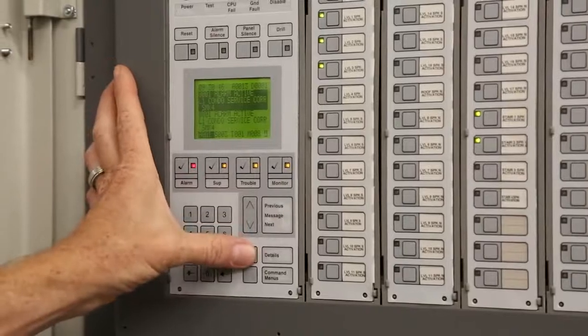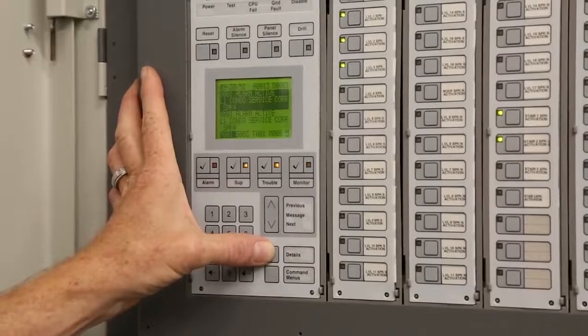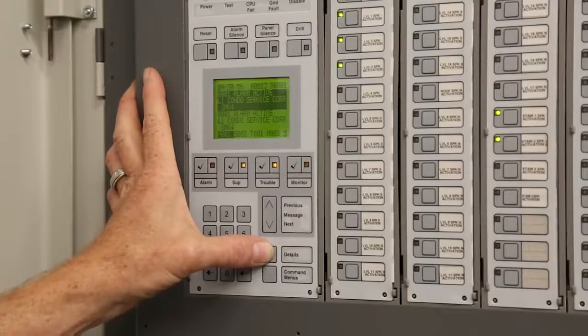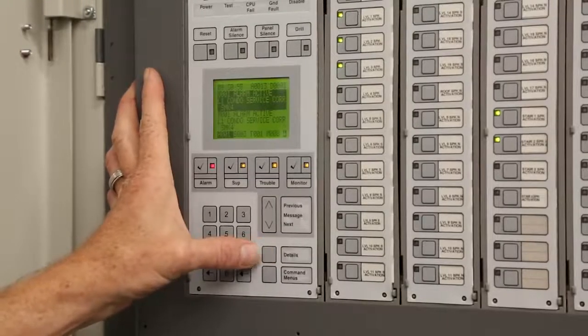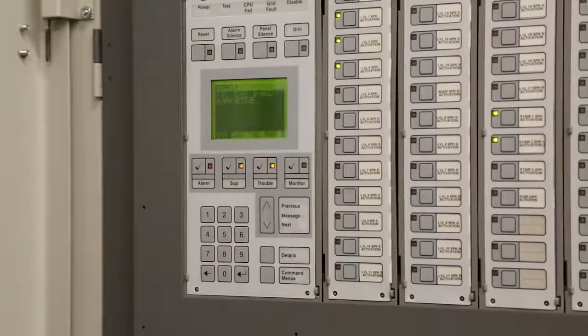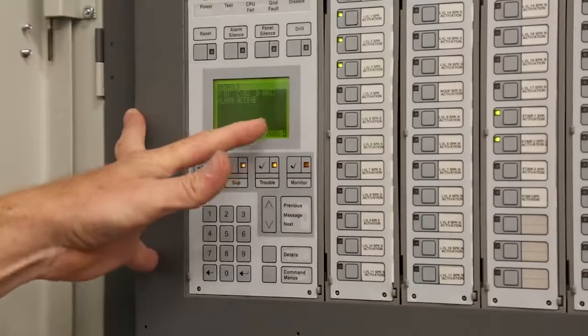If you're not quite sure, first of all, you go out to that detector. The one that's flashing red is obviously the one that's picked, okay? If it's up higher and you can't actually see it and you see the number, remember I told you you can always go to details. Whatever's highlighted, we can go to that. So right now we know it's from panel 1, card 2, device 33.